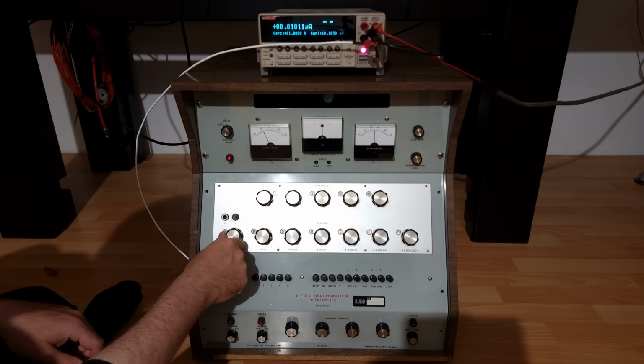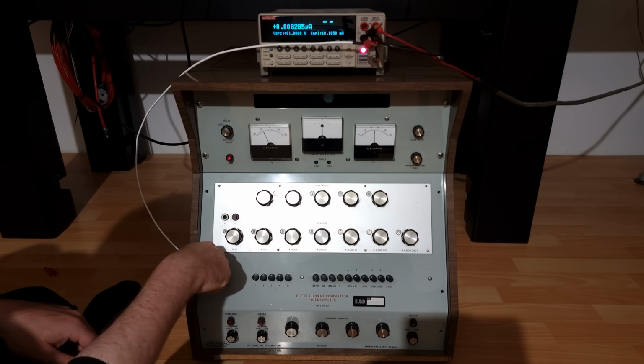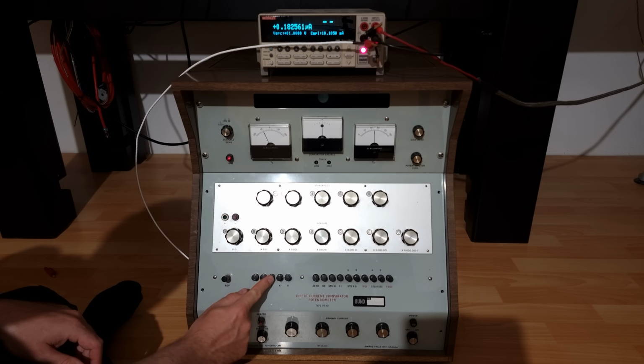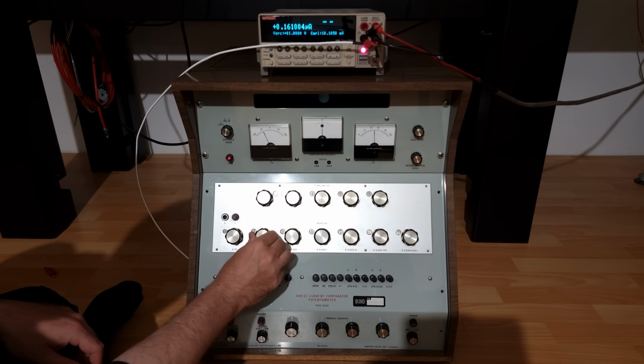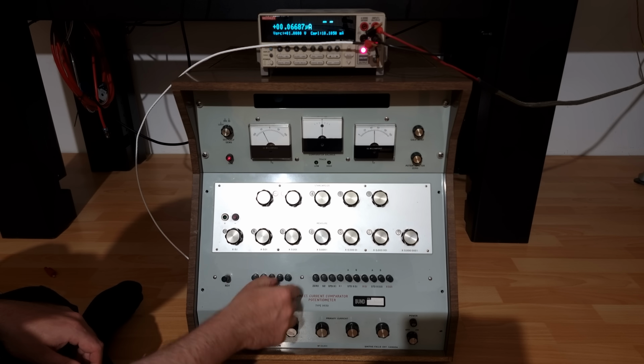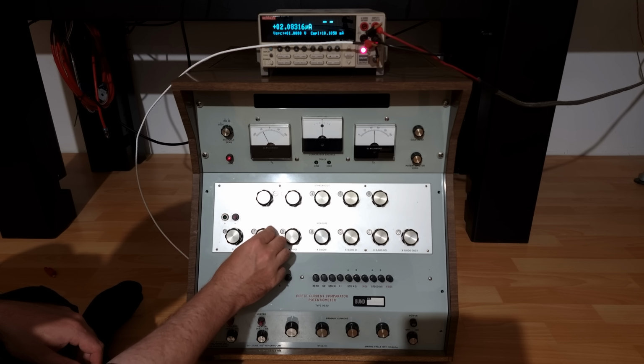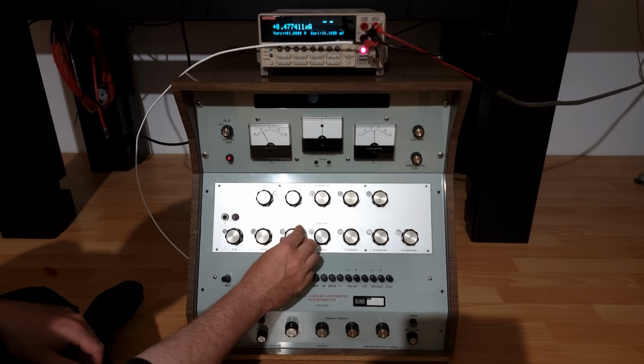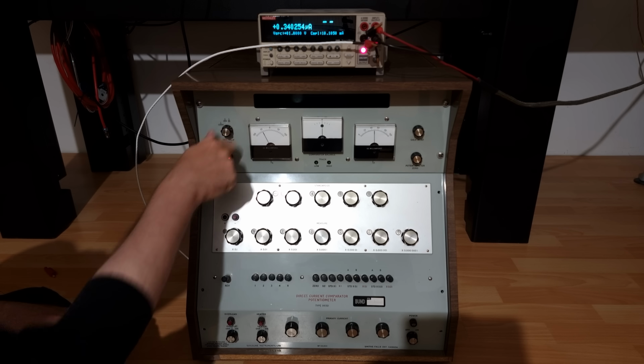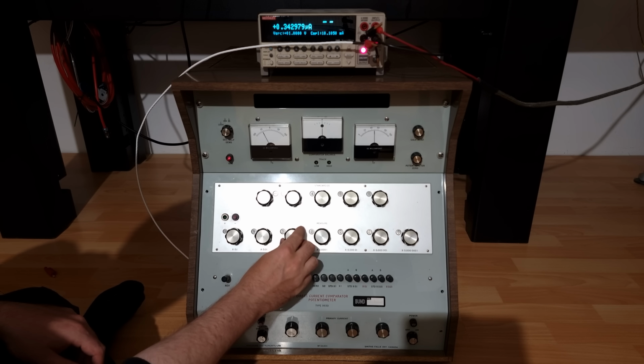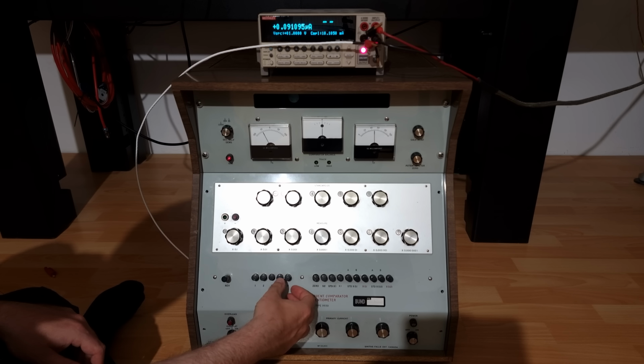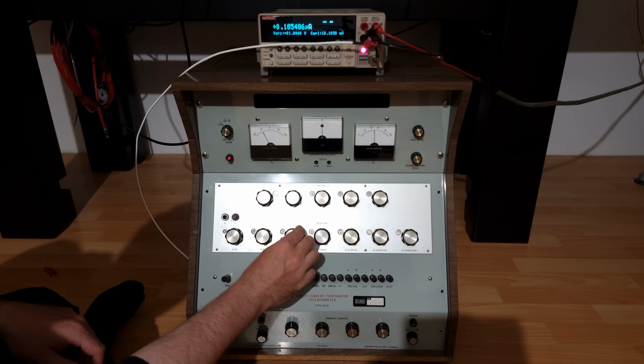The 1, 2, 3, 4 and R push buttons on the left side are sensitivity settings before the Nanovolt preamp. So if we don't know the voltage that we are measuring, we can search a wide range without blowing anything up. The push buttons on the right side are functions and ranges. Times 1, times 0.1, and times 0.01 select which forcing resistors are placed into the path of the secondary current. Therefore, they are the voltage measurement ranges. 2 volt, 200 mV and 20 mV, and that's all the voltage ranges there are. The upper left-hand rotary switch is a sensitivity setting after the Nanovolt preamp. So just a divider for light beam galvanometer sensitivity.